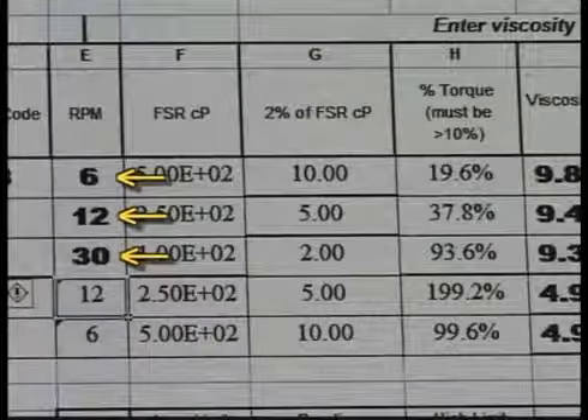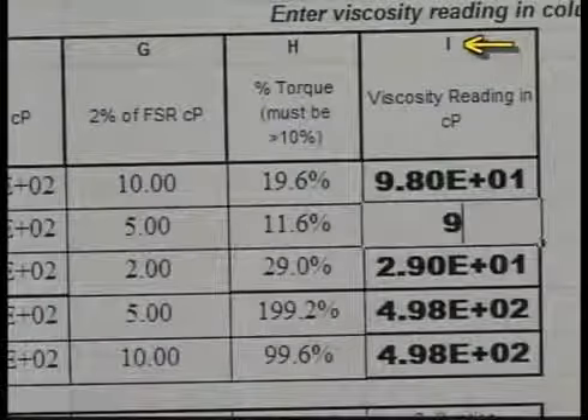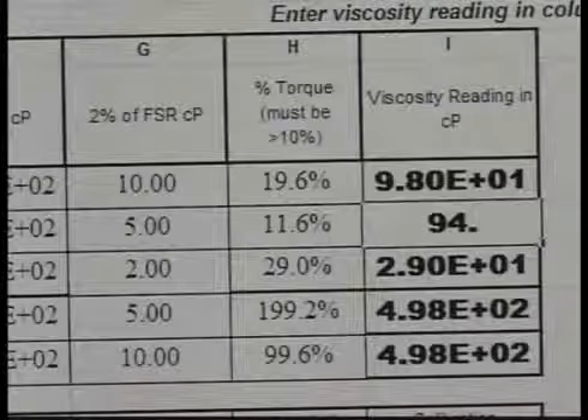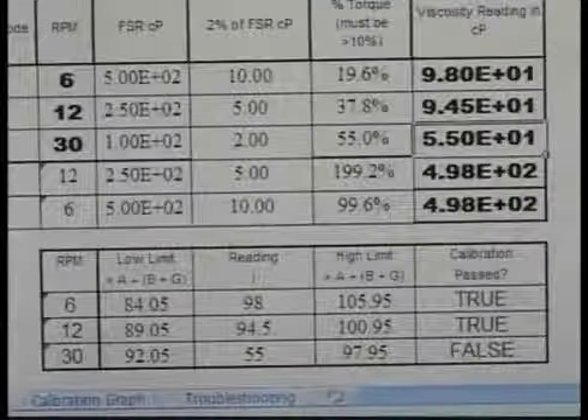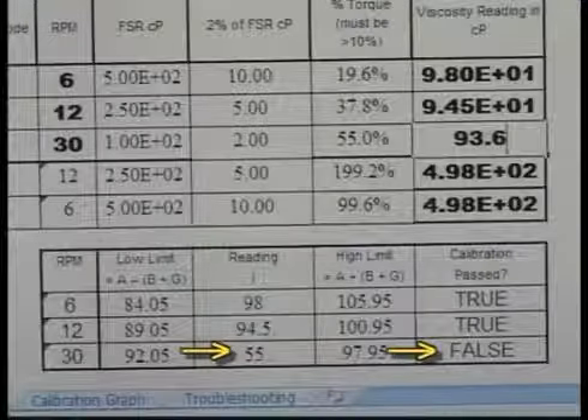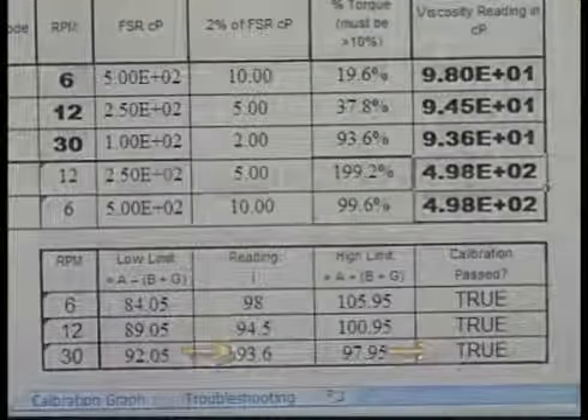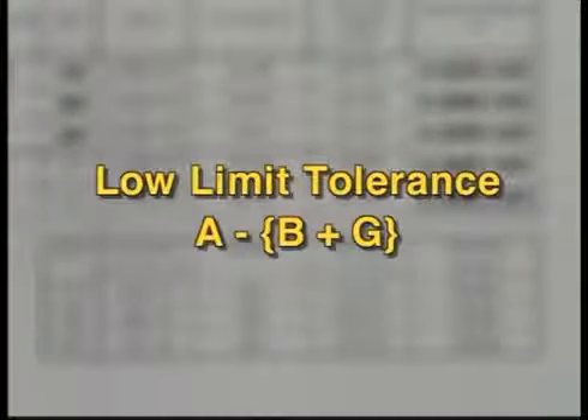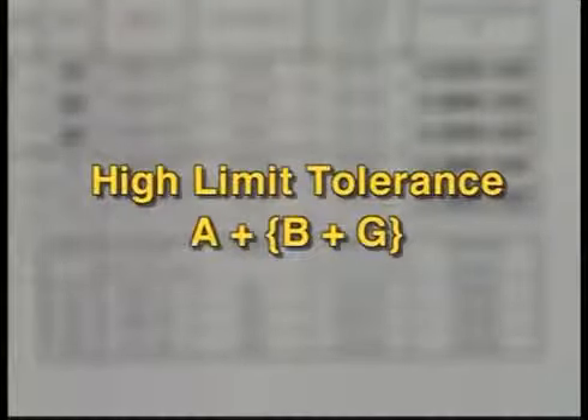Now, run the 3 speeds you have selected. Record and enter the data in column I. Your results will show up in the box below. The low limit tolerance is column A, the actual fluid value, minus column B plus G, which is the 1% value of the fluid plus the 2% value of the full-scale range. This high limit tolerance is merely column A, the actual fluid value, plus column B plus G, which is the 1% value of the fluid plus the 2% value of the full-scale range.